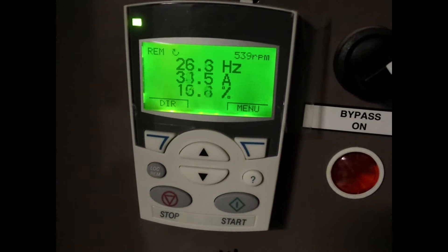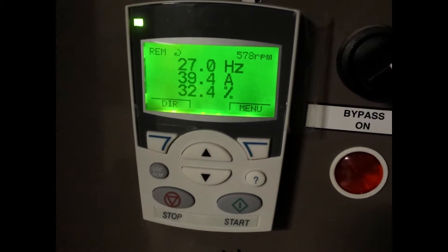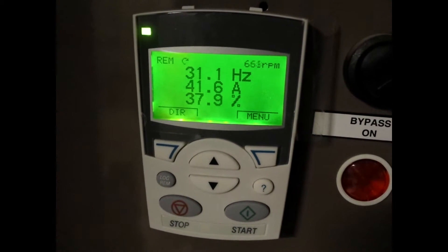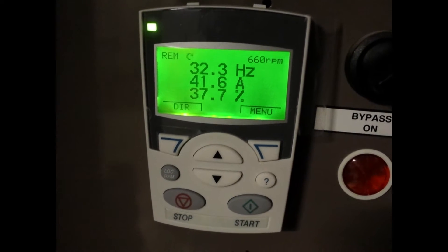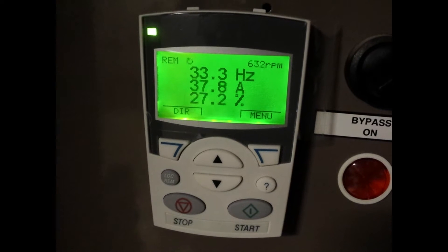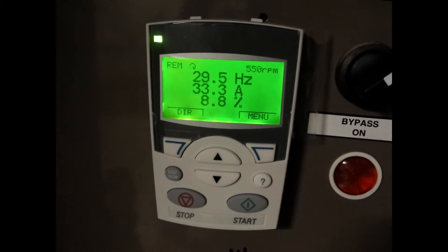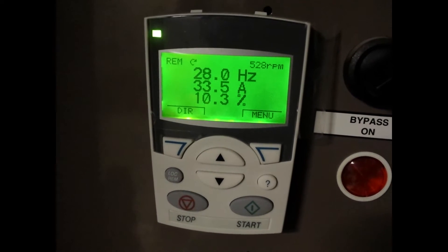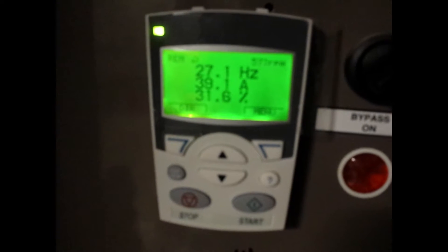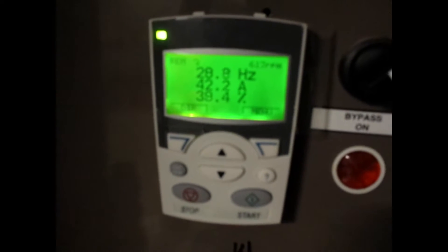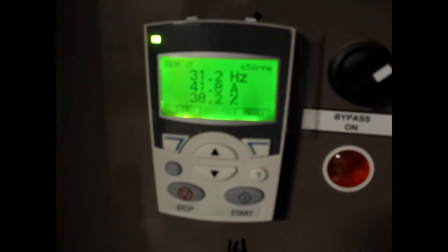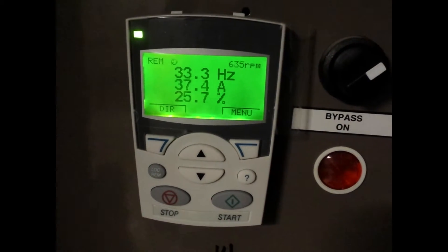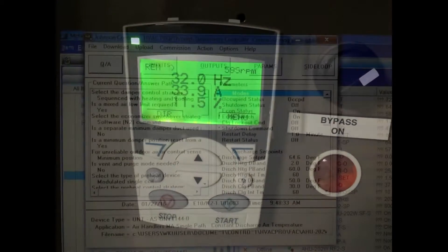Here we are looking at a supply fan drive that has a lot of fluctuation in the set point. We can see it bouncing just up and down all over the place. What we're going to do is use the auto-tune feature in HVAC Pro to level out the PID loop.